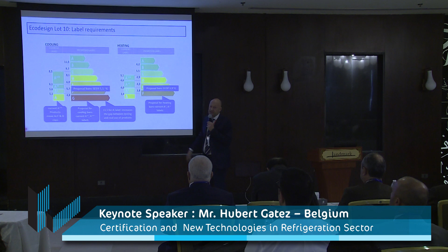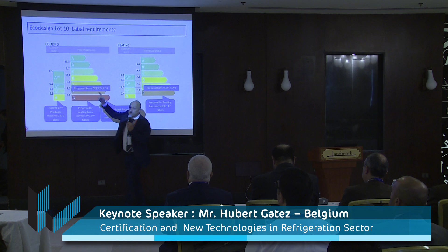When you look at the situation today in Europe, when you have an EER or COP exceeding 5.1, you can categorize your product as A+. When you have above 5.6 it is A++, and so on and so on. It is just to make a category between the units to show this is efficient or this is less efficient. What is the proposal of the European Union for 2018? It is to change the scale. It's to say, from 4.8 you are F, from 6.8 you are D, and so on and so on. And you can see that to become A, you need a COP of 11.5.